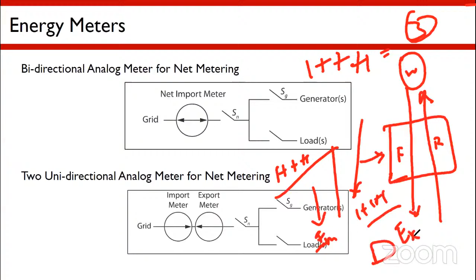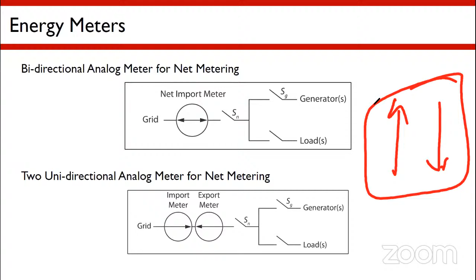In the bidirectional meter, the advantage is that the forward current is calculated in a separate counter, and the reverse current is calculated in another separate counter. The forward currents added together show you the import energy, that is E import. The second counter shows you the E export, the energy exported. The export is subtracted from the import, and that gives the net energy consumption. So this is the concept of the net meter. It is called a bidirectional meter because it can record both the import and the export in the same meter in separate registers. That is the main difference between a normal meter and a bidirectional meter.